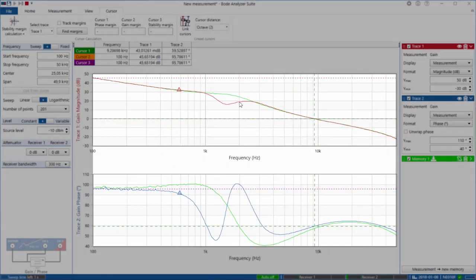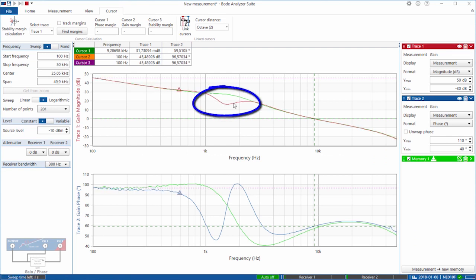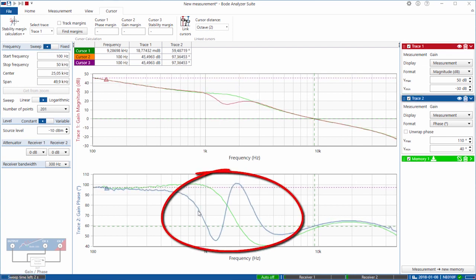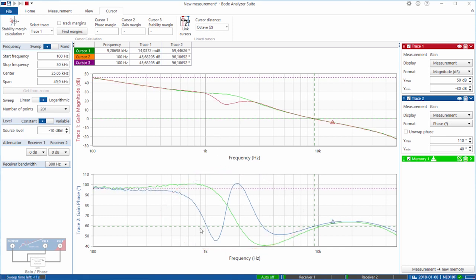So now, on this red trace, this is the resonant frequency of the LC inside of the LISN. You can see that the loop, the gain has dipped. But look at what's happening with the phase. The phase is going wildly up and down and that is because now Z_out of this LC network is interacting with the control loop of the power supply, just like Professor Middlebrook suggested.